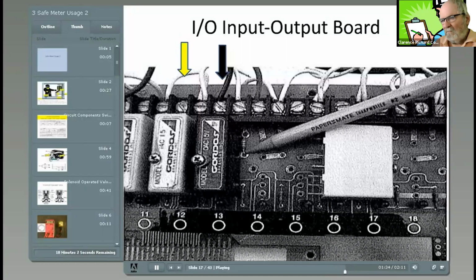The yellow modules are 120 volts AC input modules, connected to limit switches on the plant to report the position of gates, etc. The yellow input modules have corresponding LEDs that illuminate when the limit switch input supplies 120 volts AC to their terminals. If the limit switch places 120 volts AC at a terminal, expect the LED to illuminate. If the LED does not illuminate, change out the fuse or yellow module. Sometimes the modules are different colors, sending or receiving different types of signals than described above.